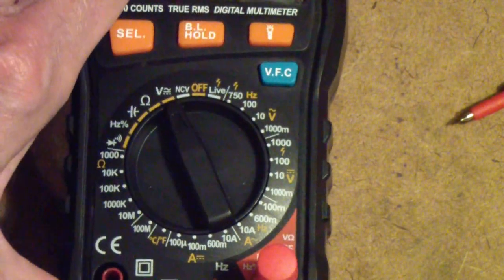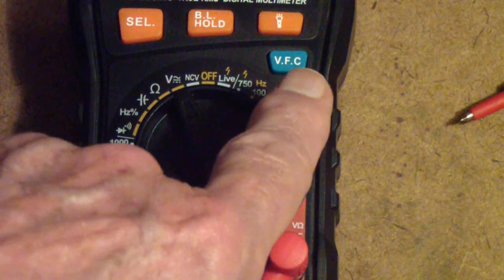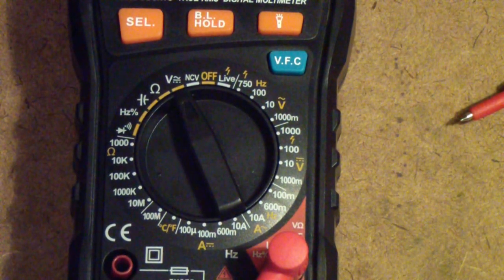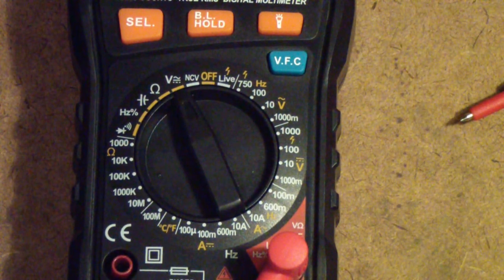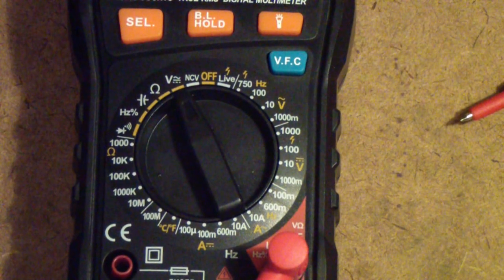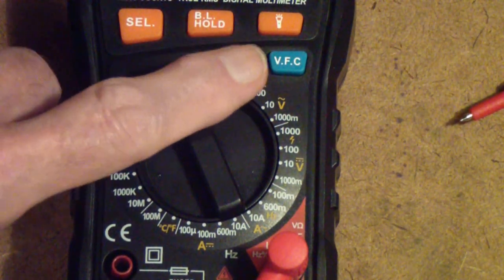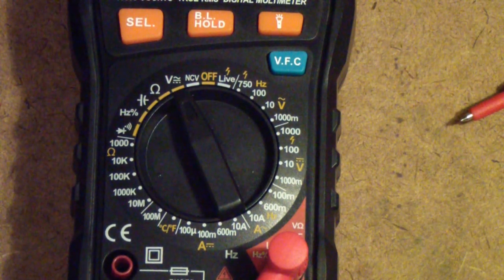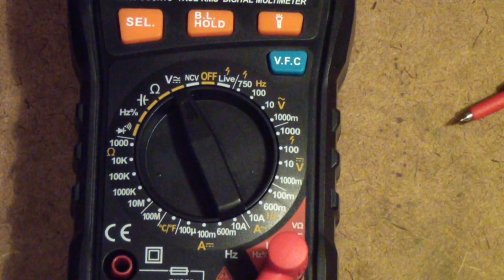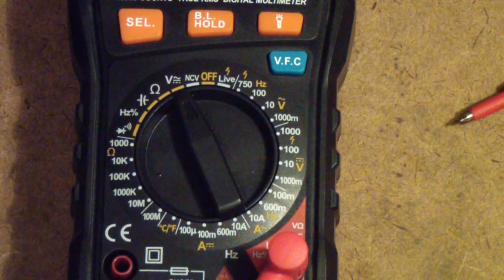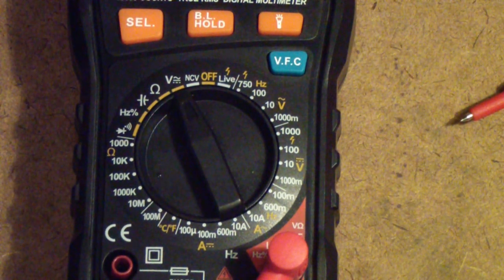Before I close this, I want to mention this VFC feature. The instructions in the manual aren't very clear on this, but this is a feature that Fluke introduced—I'm not sure if they invented it. With a lot of motor control circuits these days, the AC line is brought through a controller that converts the power to a pulse width modulated signal. This allows you to vary the speed of a motor without significantly affecting its torque, so in other words it doesn't lose power, it just slows down.